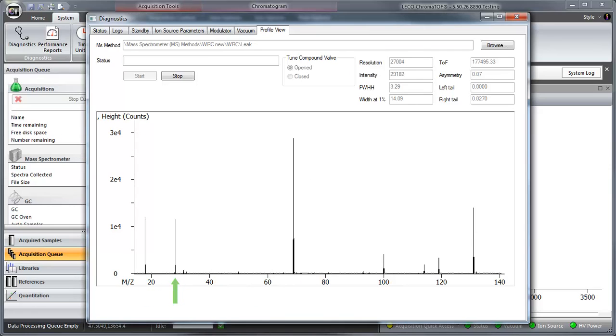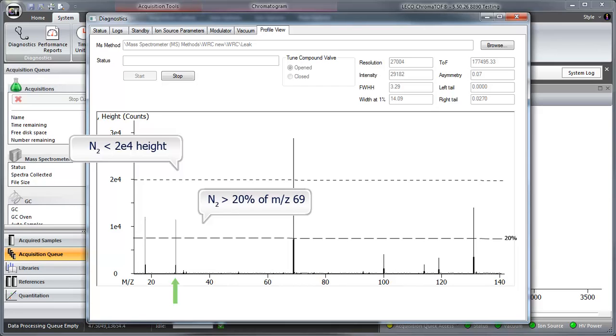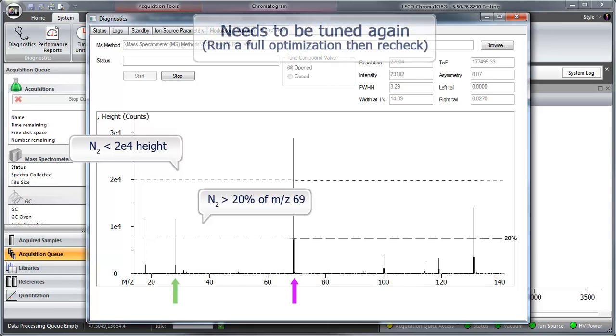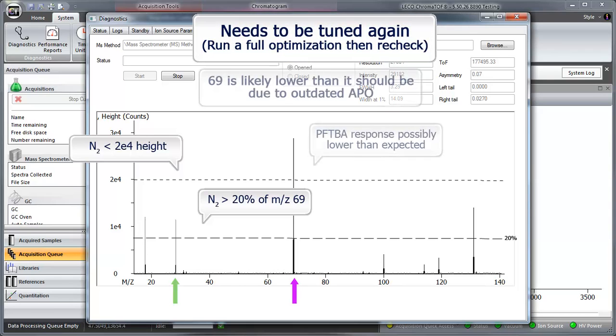If mass to charge 28 is less than 20,000 height counts, but still greater than 20% of mass to charge 69, it is unlikely a leak exists, and instead the instrument might need to be retuned. Run a full optimization sequence, then re-evaluate the profile and see if the peak ratios have improved.